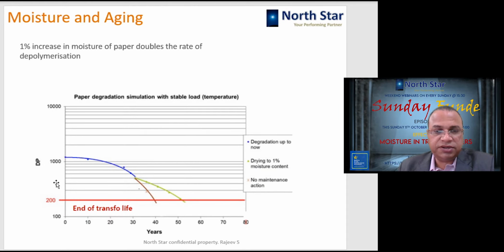So if we look at the impact of moisture on the aging, you can see here this is the degree of polymerization, and here the number of years of the transformer. If the moisture in the insulation is say around 2 to 3%, then the transformer is following this life path, and if this continues then it will die at an age of around 40 years. If we dry the transformer out and keep the moisture within 1%, then it will live a further 10-15 years, and it will serve us up to 50-55 years of life.